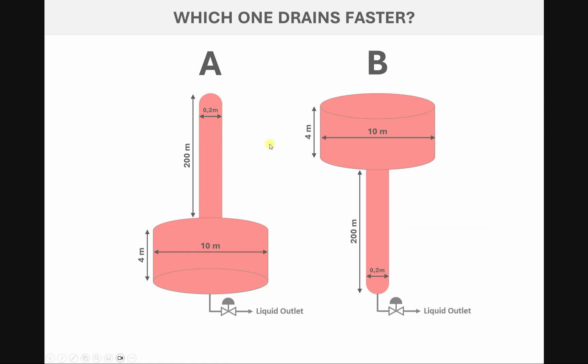Before going to the simulation, I want to mention one key point. To find out which one is draining faster, we need to see what is the drainage capacity. The drainage capacity is governed by the valve here. So the valve CV and the differential pressure across the valve are the key factors.